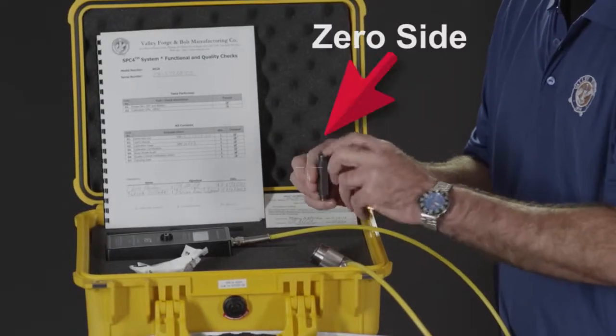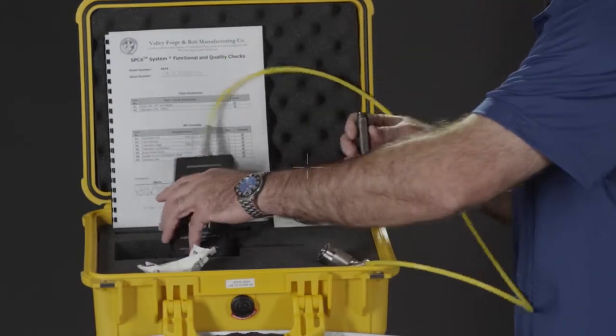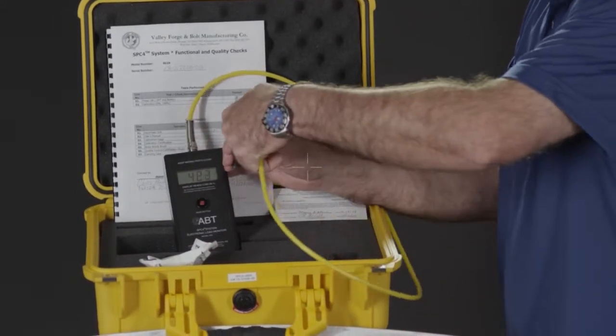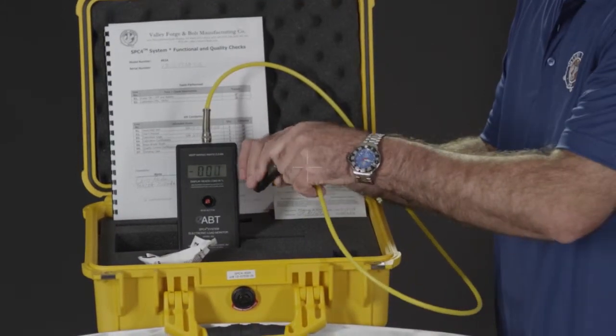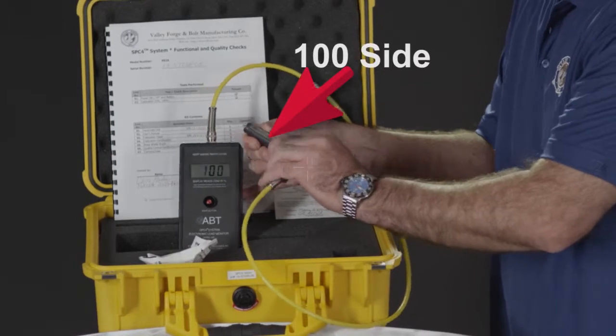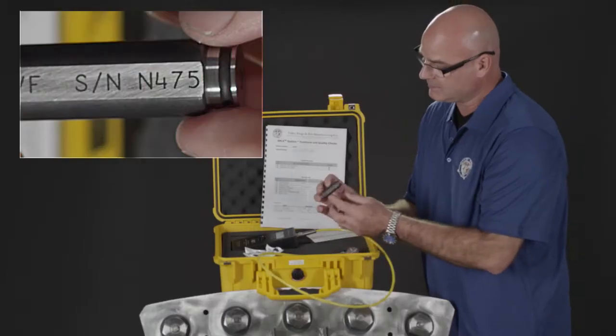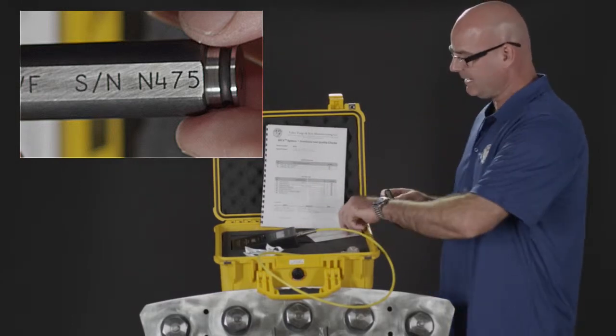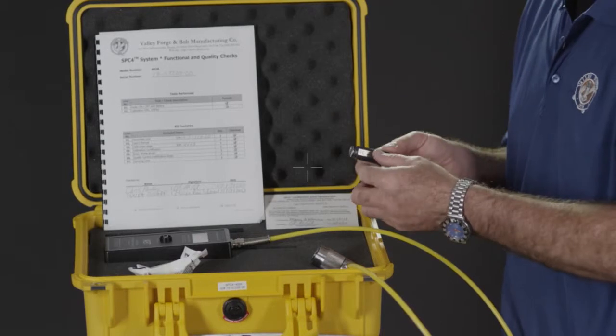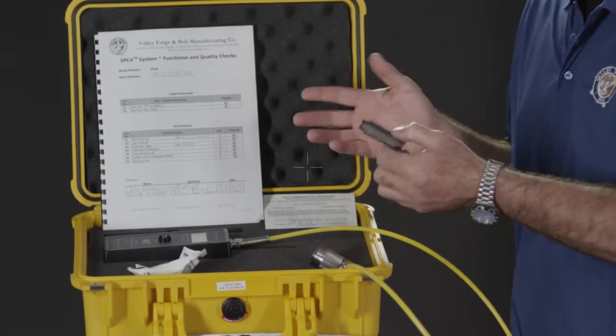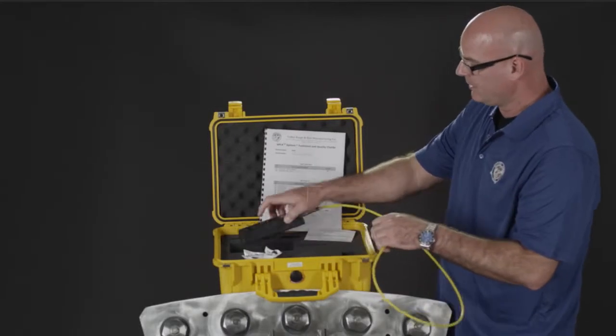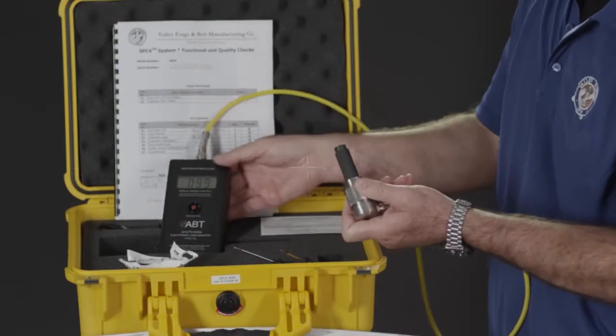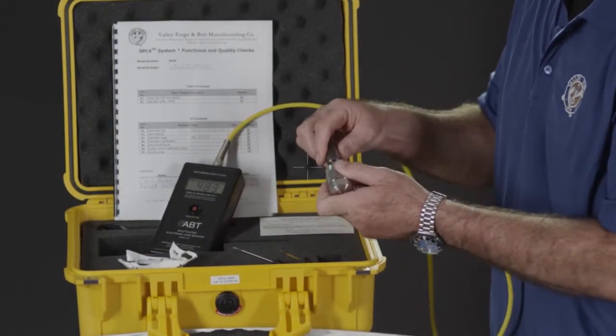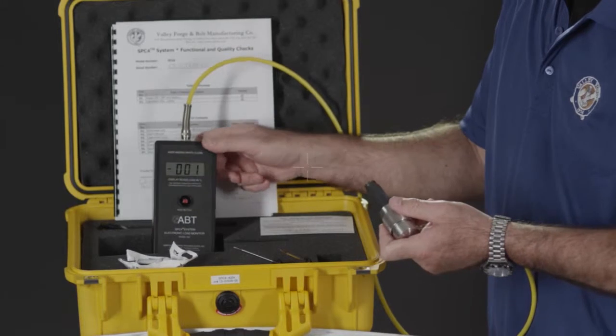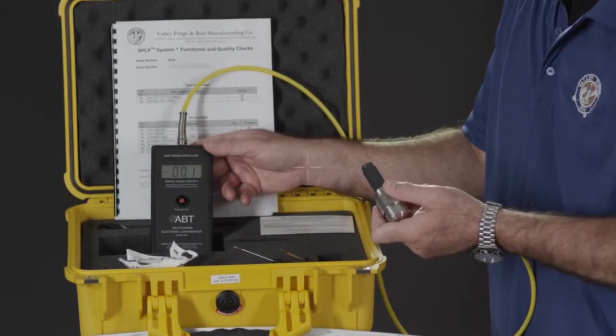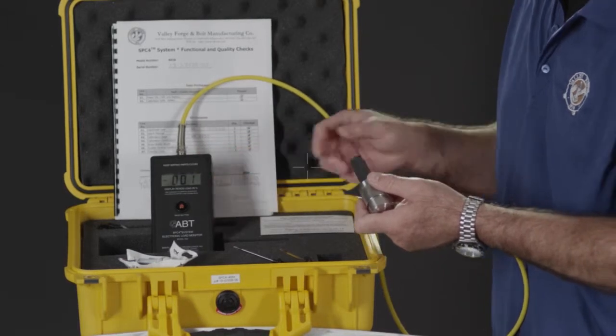Basically it has a 0 side, and you can clip on your fastener, turn your meter on and clip it on and read a simulated 0, and then you can clip it onto the 100 side and read the 100. It also has a serial number on it, and that serial number correlates to a certificate that has the serial number, and for ISO programs can be sent to us and calibrated once a year. You can zero it if it's off, and I'll go over that. And when it doesn't read 100 or 0 when you're actually checking it, this one's off by just 1 point on the top end and the bottom end. You need to do a calibration or an adjustment to the unit, okay?